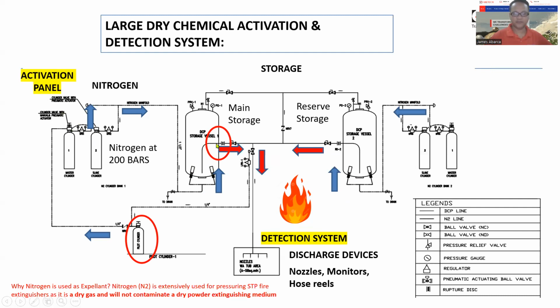Then it will break the burst disc. When that burst disc is broken, it will now be discharged to the nozzles on the protection area. Another way to activate this is manually, using a bottle of nitrogen.